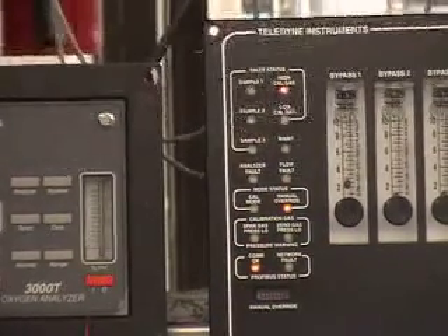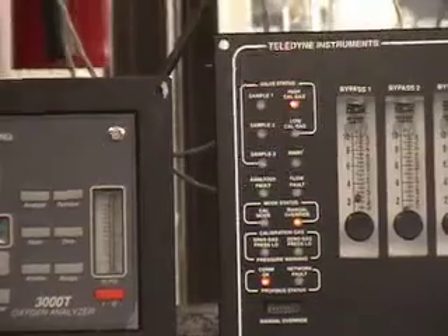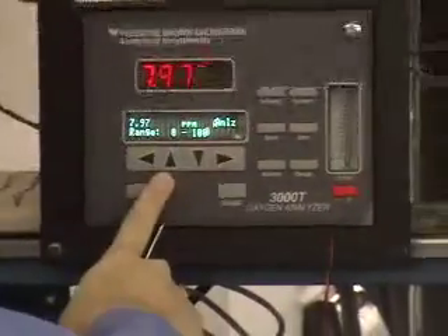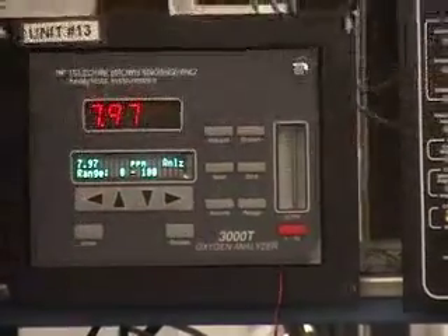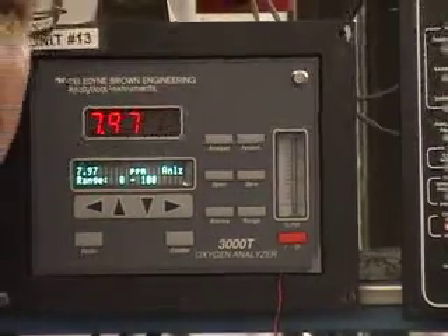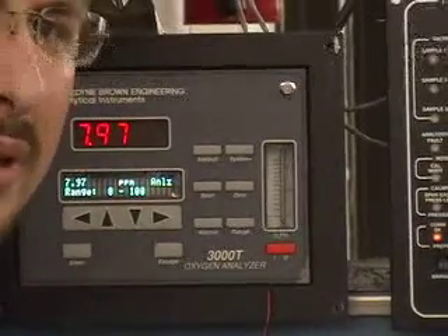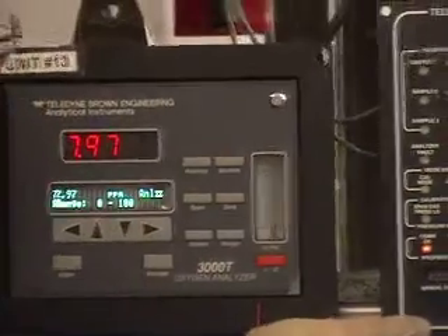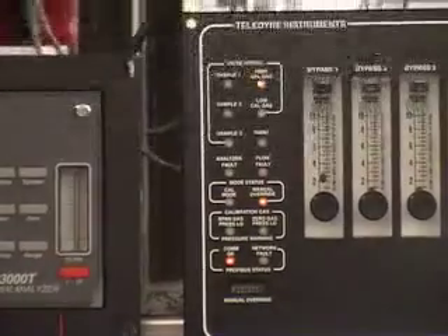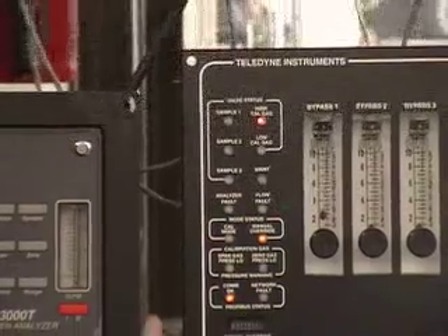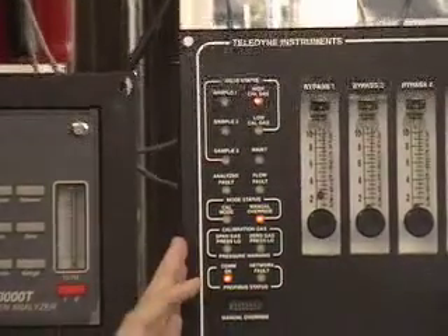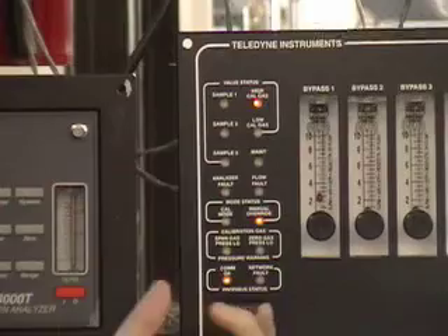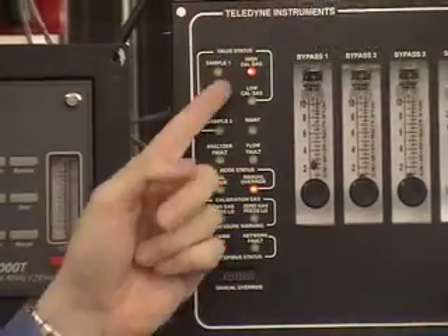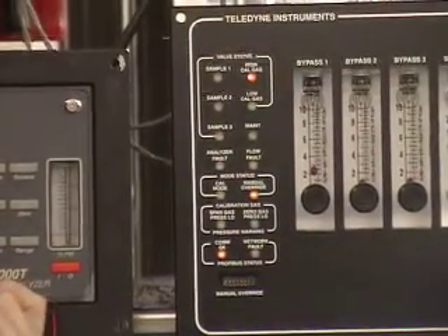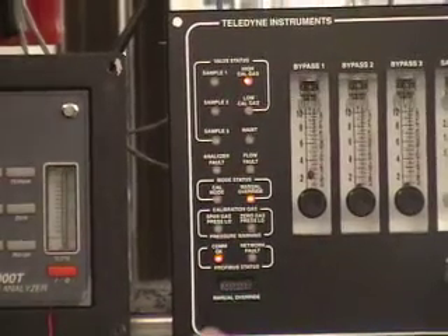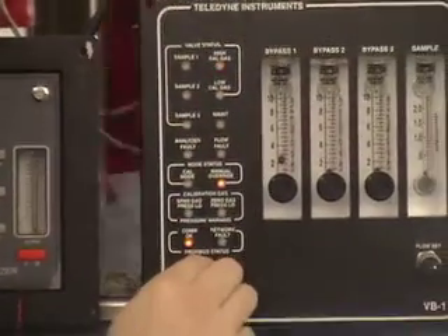And notice here, very important to notice, in the manual override the analyzer did not go into span mode when I flipped the cal valve on. That's not true when I am in computer override. When I'm in computer override, doing that could send the analyzer into span. But right now, we are in full digital mode. We are not in computer override. This is just manual override. So this will only flip the valve on, it will not send the instrument into calibration. The same goes for the zero valve.